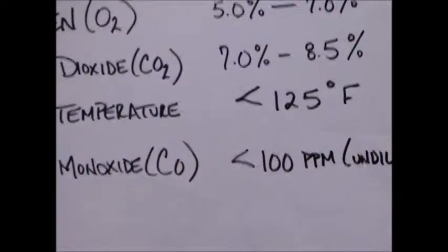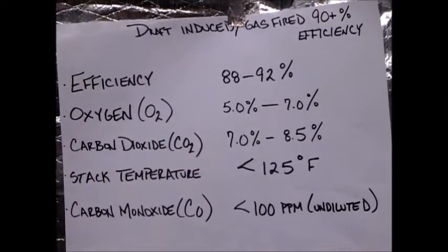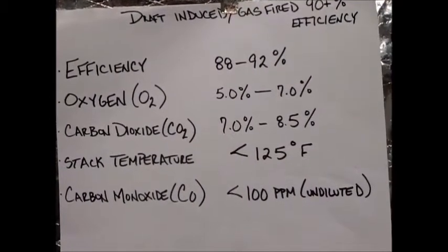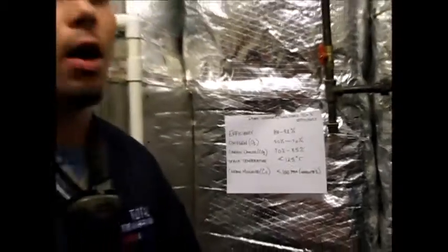Anything under 100. If you start going over 100 parts per million with the carbon monoxide it indicates safety issues, maybe blocked vents, not enough air getting to the system. Just lets a technician be a technician at that point to figure out what's going on.